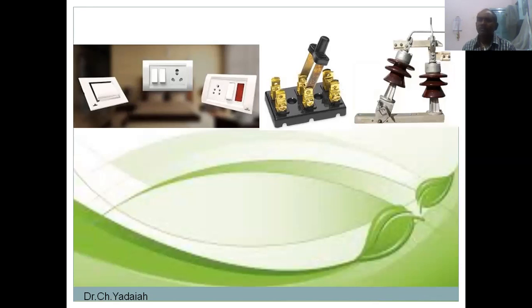And coming to higher current, have you observed this one? It is an AB switch, the air break switch. You can observe this type of switch where current is more than 100 amperes, in DTRs, in plinth mounted substations or double pole structures. These AB switches are used to operate at voltages up to 11 kV under low current. That means it can operate under load also.